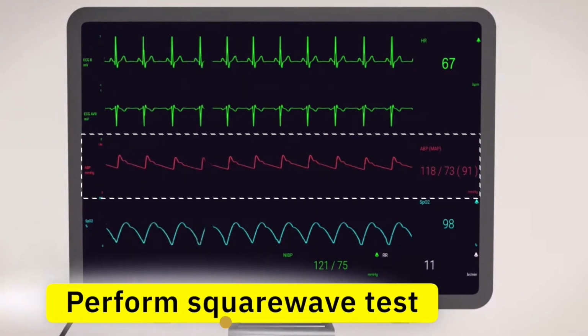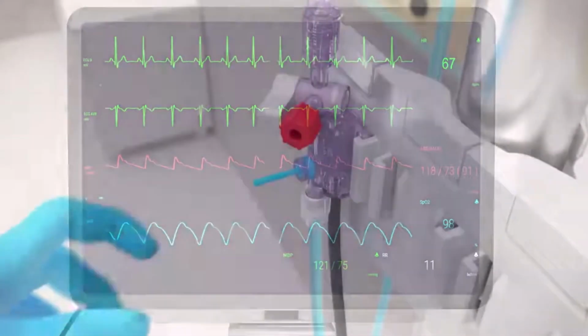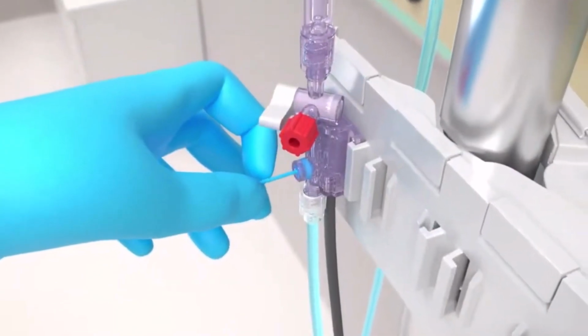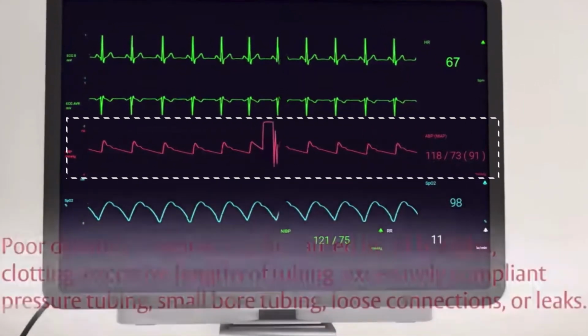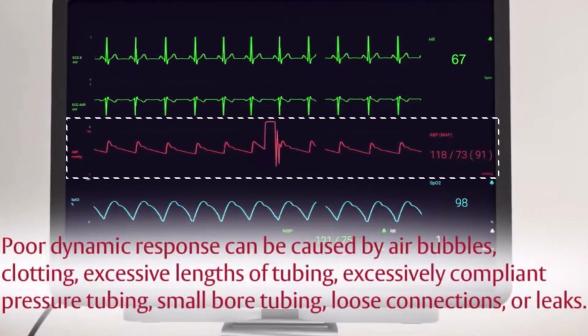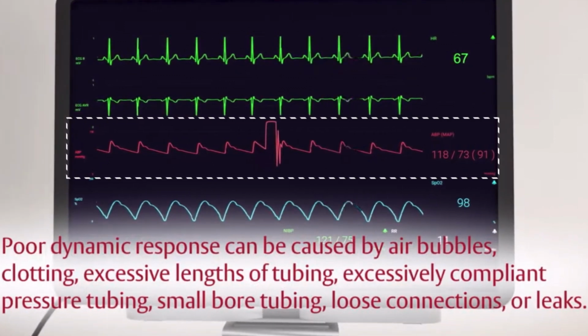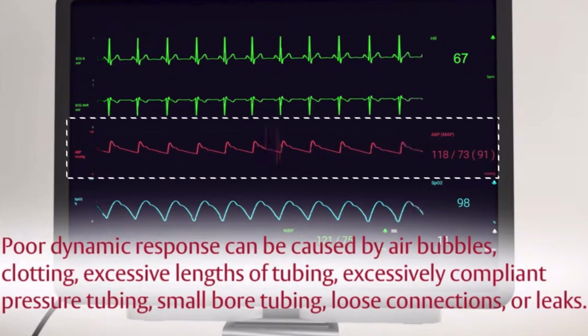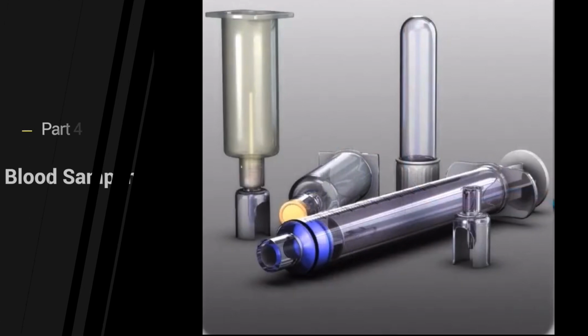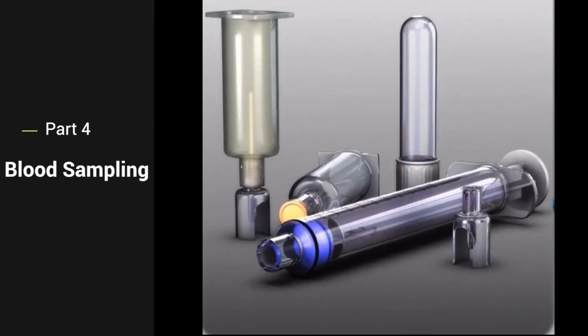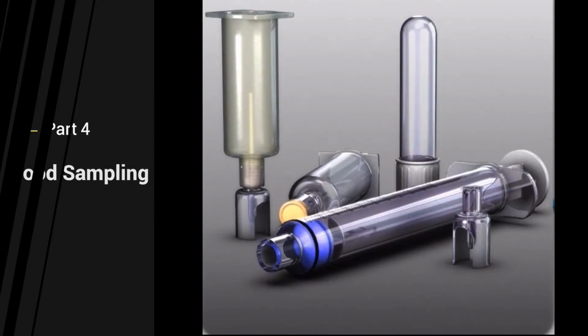Perform a square wave test to assess the frequency response of the system by pulling the snap tab and releasing quickly. Confirm the pressure channel has the appropriate label, scale, alarm settings, and color coding for the physiologic pressure being measured. For blood sampling, you may need to obtain a direct draw unit, blood transfer unit, and collection tube syringes, as well as alcohol preps and a needleless cannula.